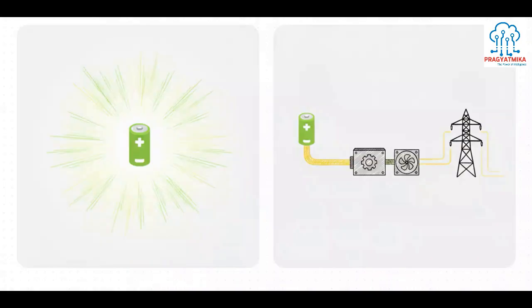Out in the real world, commercial projects use AC efficiency, which measures performance at the actual grid connection. Because AC efficiency has to account for the inverters, the transformers, and those power-hungry cooling systems, it drops down to around 85 to 92%. If you're out there modeling your financial returns based on DC efficiency, your project economics are going to be severely miscalculated.